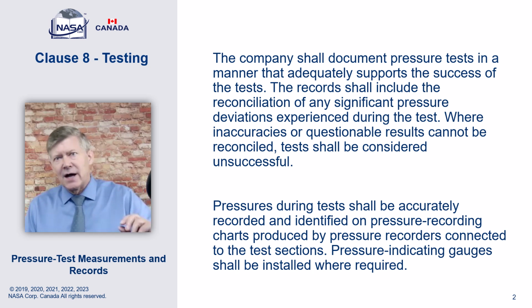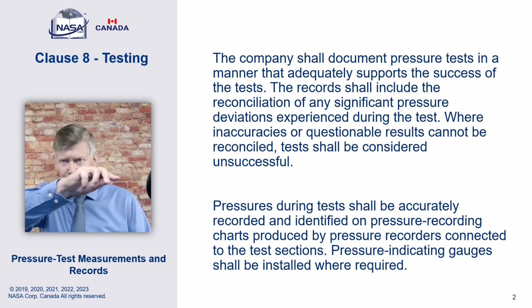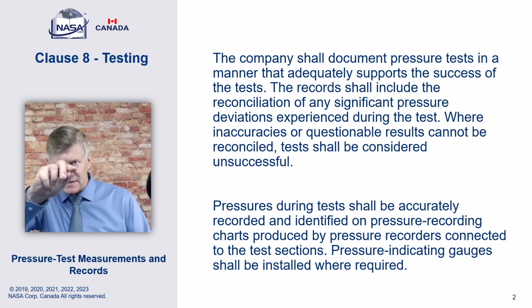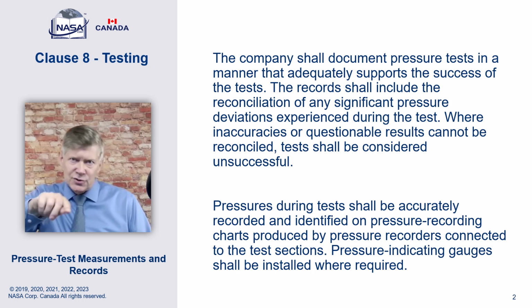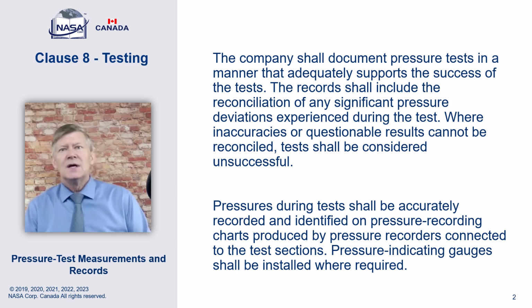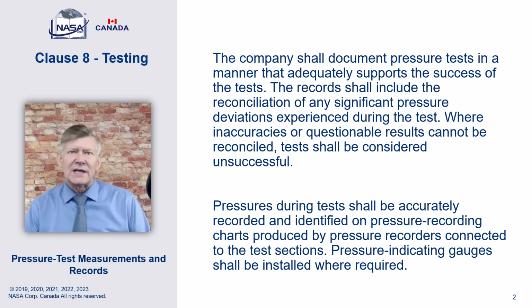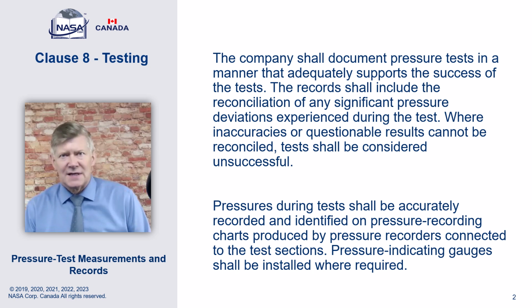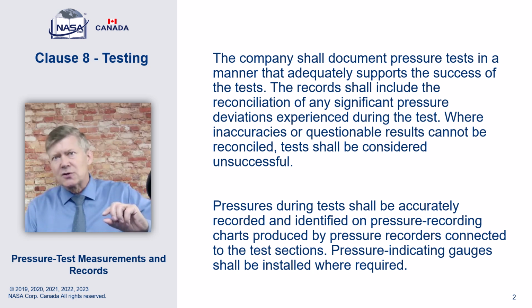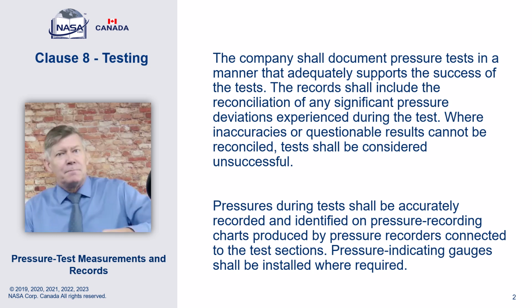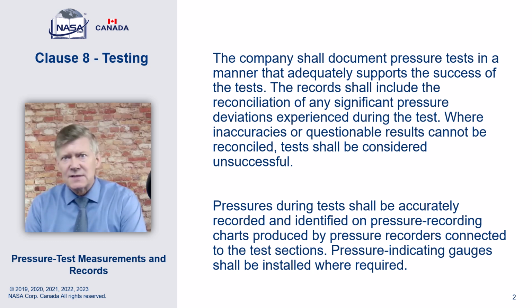Their rationale was that they were, rather than measuring center to center, right? You know how when you have an ink pen, it bleeds a little bit either side of the center line? They, at the conclusion of the test, measured the bleed inside to outside, determined that the drop in pressure over 24 hours was less than 1%, and said that that was insignificant. We looked at it and said that, well, no, it's closer to 2.5% if you measure the drop in pressure center to center, but even 1% in 24 hours is significant.